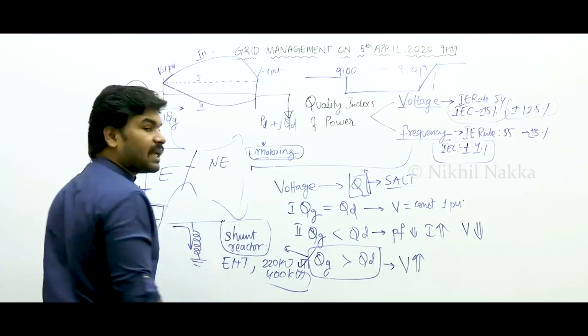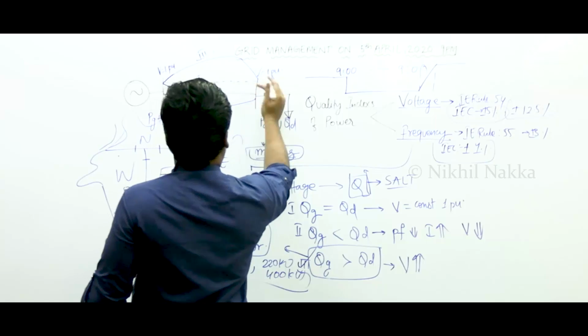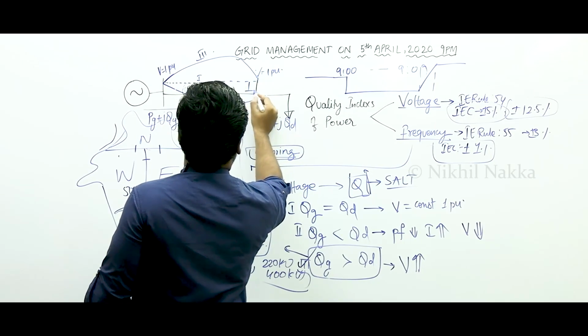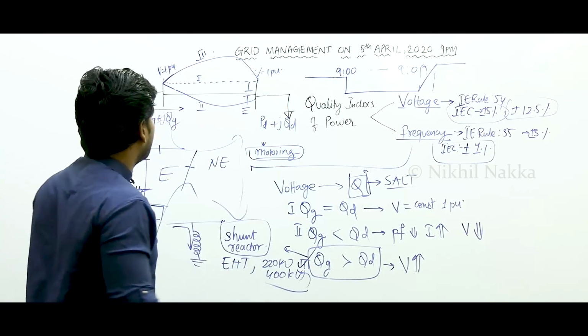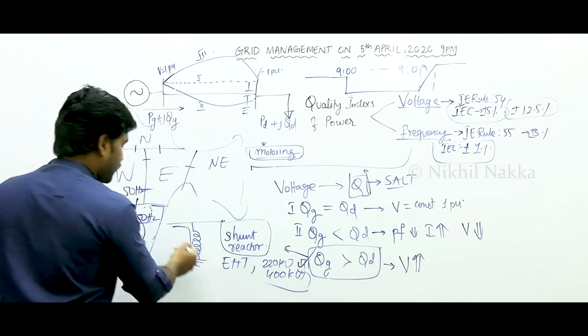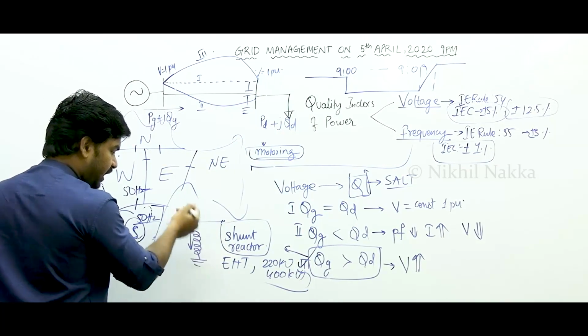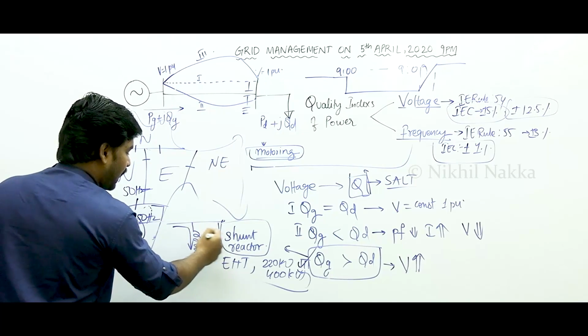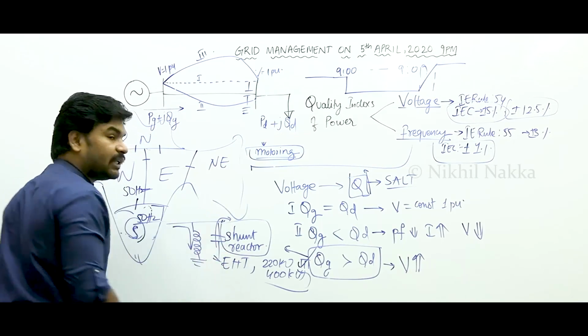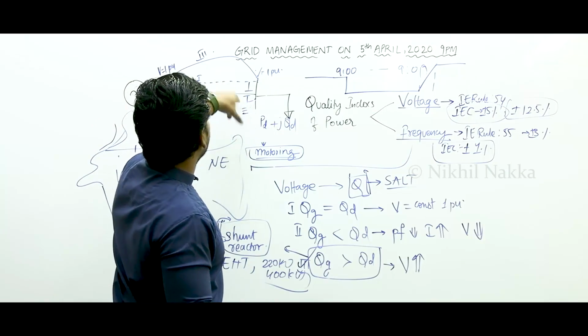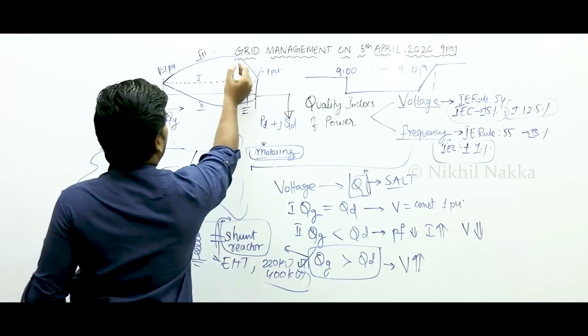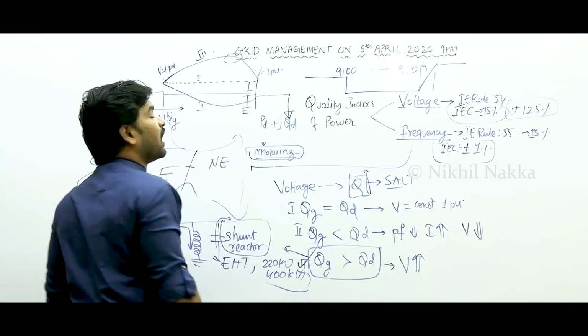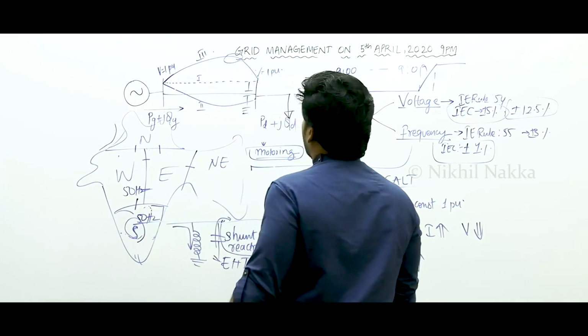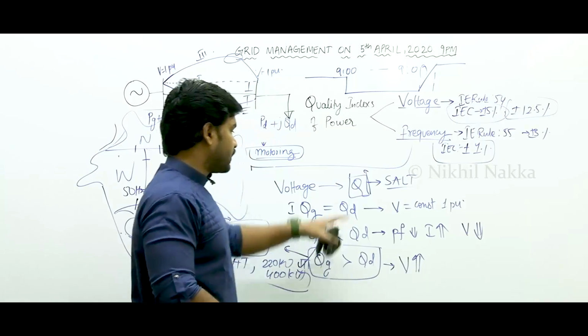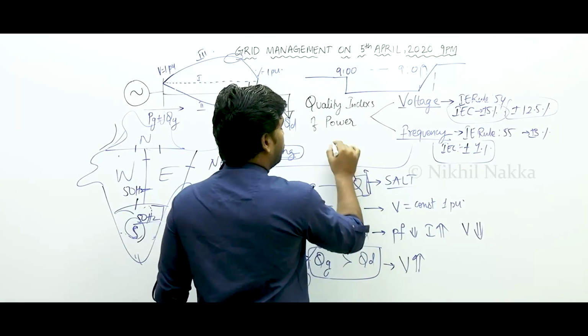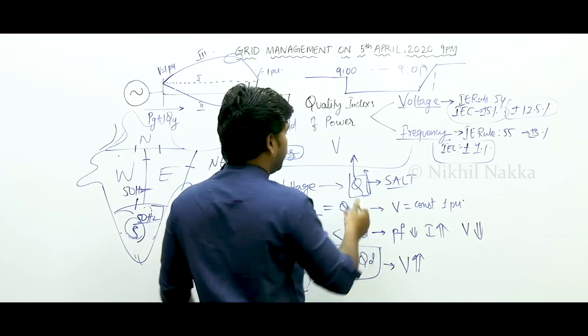Inside the transmission line there is capacitance, and all this capacitance adds up, with the maximum capacitance generally assumed to appear at the load end. A capacitor, unlike a parallel inductor which consumes reactive power, can deliver reactive power. So it injects a lot of reactive power, and hence at this point in the line you get high voltage. Now, there is another quality of reactive power you may already know - reactive power always travels bidirectionally in a transmission line.